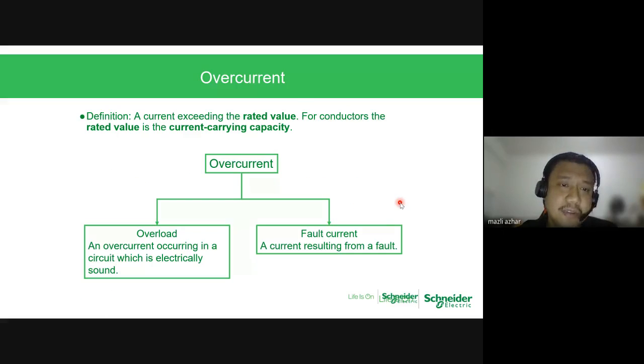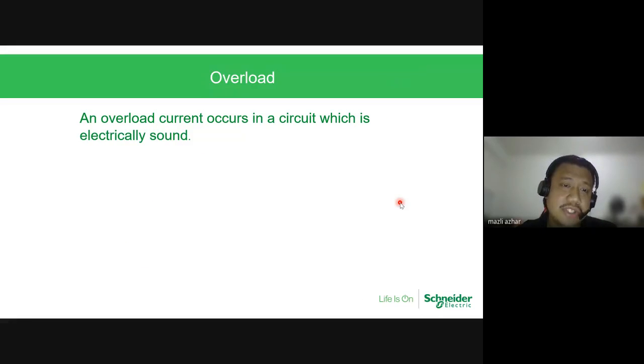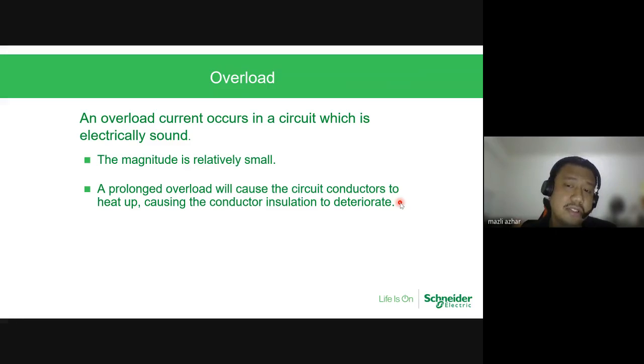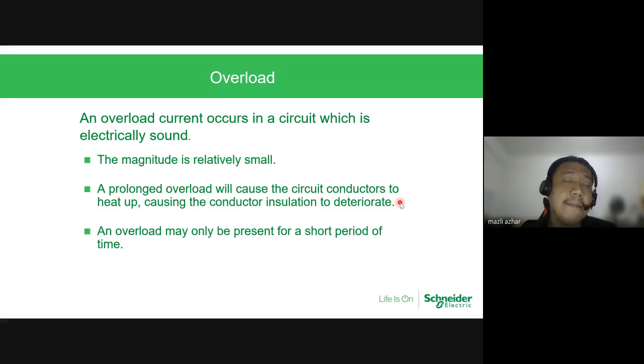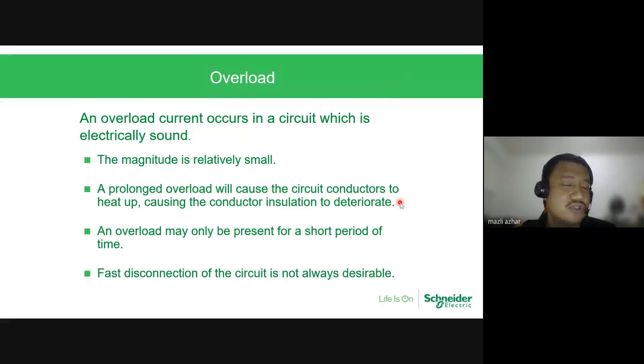So overcurrent is a current exceeding the rated value. It can be divided into two: overload and fault current. Let's go to overload. It is an overload in a circuit which is electrically sound. The magnitude is small, but a prolonged overload will cause the circuit to heat up and the insulation to deteriorate. This is where it starts to catch fire, and it may be present for only a short period of time. If you recall in my previous slides, as I mentioned, there are curves B, C, D. So it is to ensure that you select the correct type of breaker for the protection. And fast disconnection of the circuit is not always desirable because the overload may happen only for a short period of time.